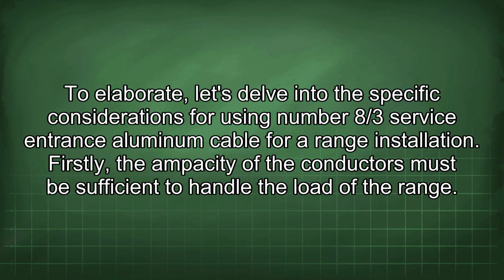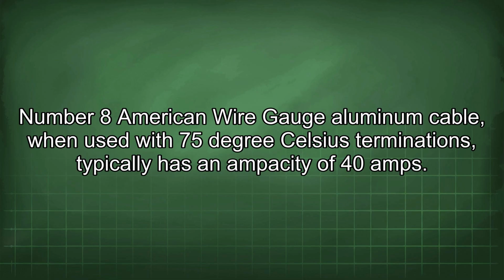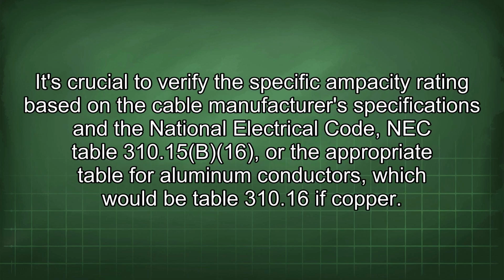To elaborate, let's delve into the specific considerations for using number 8/3 service entrance aluminum cable for a range installation. Firstly, the ampacity of the conductors must be sufficient to handle the load of the range. Number 8 American wire gauge aluminum cable, when used with 75 degrees Celsius terminations, typically has an ampacity of 40 amps. It's crucial to verify the specific ampacity rating based on the cable manufacturer's specifications and the National Electrical Code, NEC Table 310.15(B)(16), or the appropriate table for aluminum conductors, which would be Table 310.16 if copper.